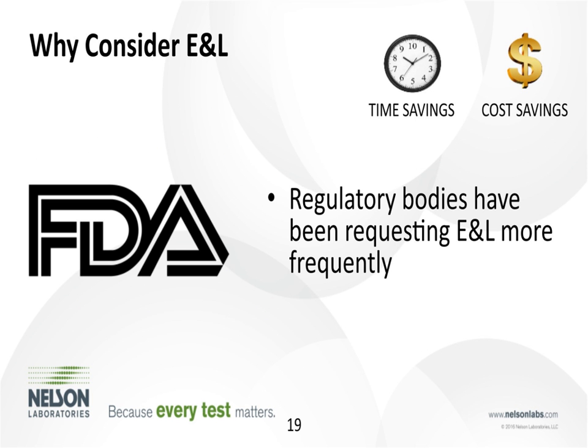Also, another thing is that we're seeing an increase in regulatory bodies requesting it. Some typical examples of regulatory bodies requesting are for respiratory contacting devices, some prolonged contacting neonatal devices, and any device made of novel material. We've also seen that it is advised when regular biocompatibility testing cannot be performed. Say part of your device is a canister full of air and it's pressurized and you cannot get any fluid down in there to perform, say, a cytotoxicity test. Extractable leachable testing of that air may be an option for you at this time.